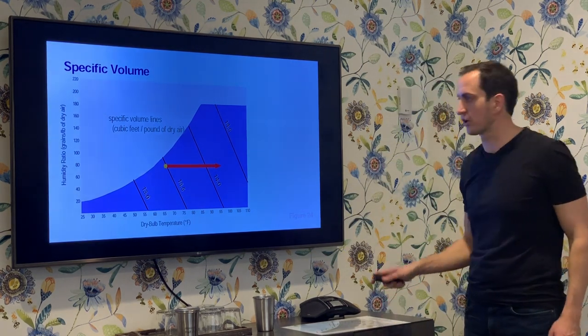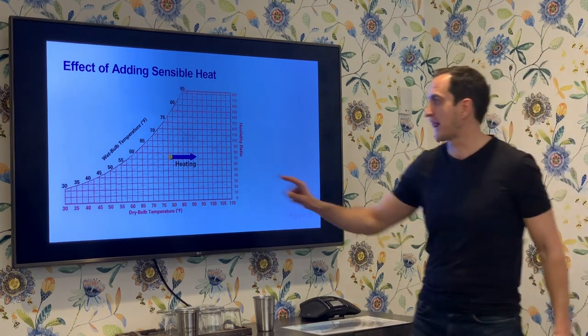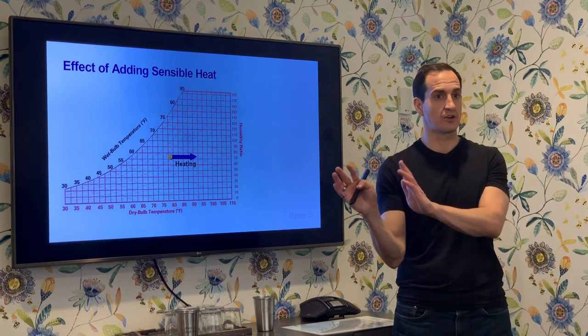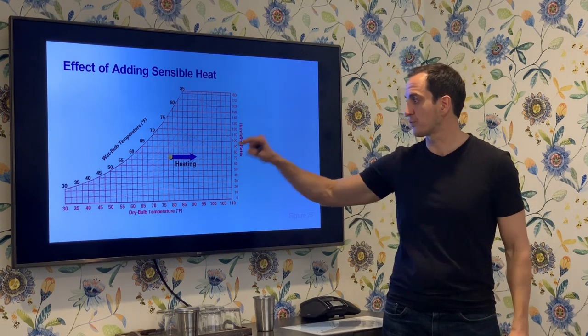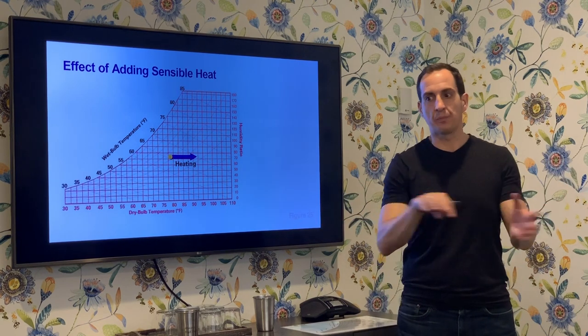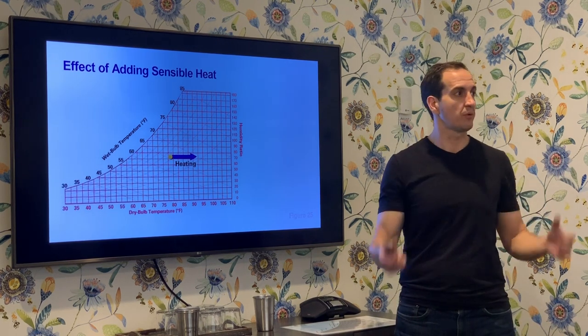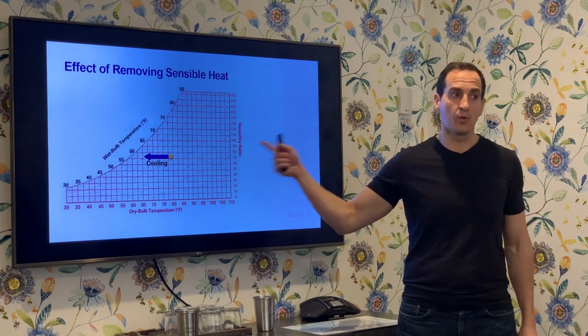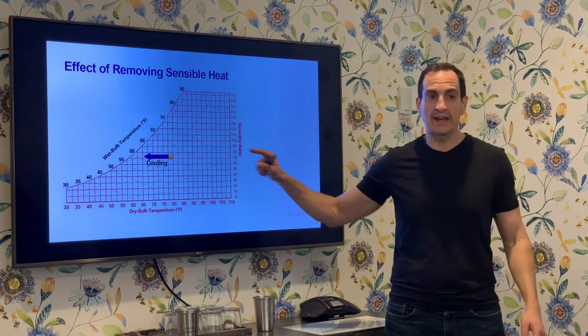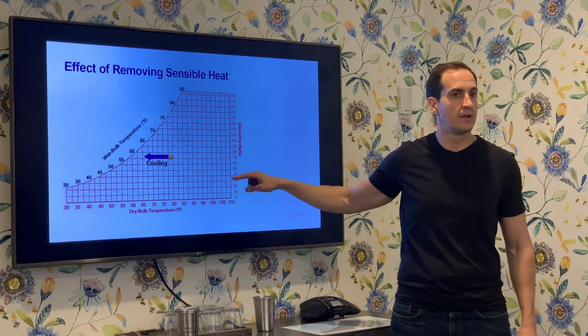Let's talk about adding and taking energy away. Adding sensible energy — dry, temperature-based energy, not moisture energy — we call it sensible heat, and we move from left to right on the chart. If we want to remove it, we go in the opposite direction. If I'm going to cool air in a sensible-only manner without removing moisture, I don't change the humidity ratio or the dew point — I'm just changing where I am with respect to dry bulb temperature.